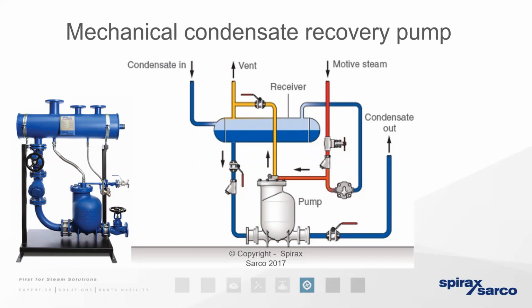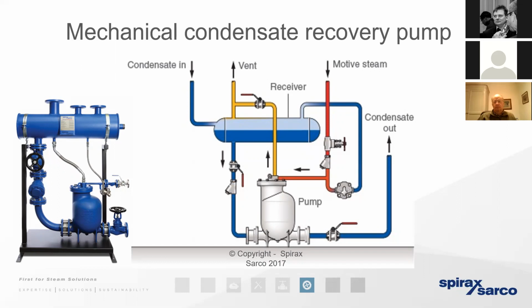25% of the time. So it's vitally important to ensure that we're sizing the pump and the condensate discharge pipework on the discharge capacity of the pump, not on its fill capacity. So that means that the discharge pipework, if we compare it to an electrical condensate recovery system, the run of pipework to pump it back can often be three times larger. So that cost really needs to be factored in whenever we're benchmarking the benefits of one pump versus the next.